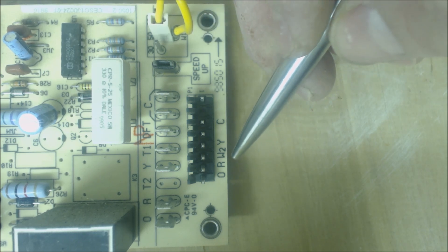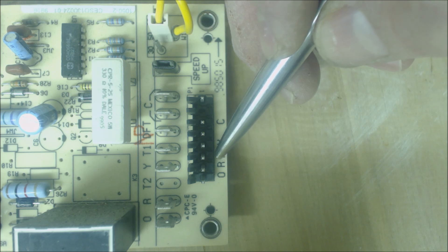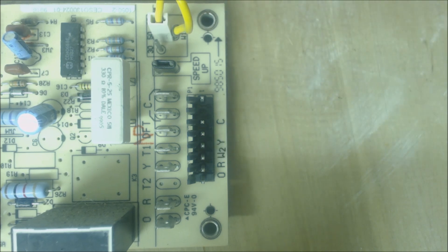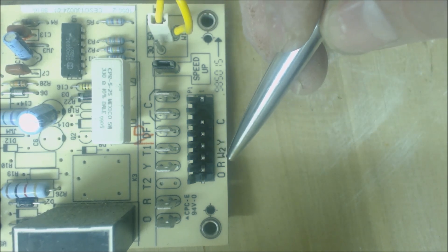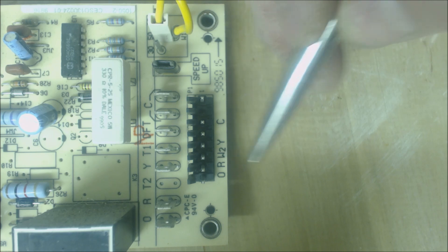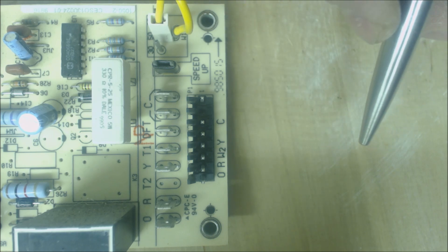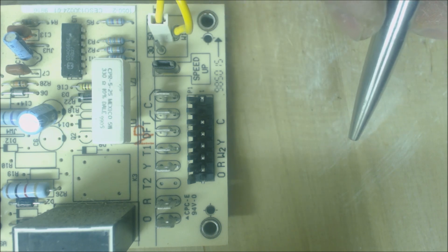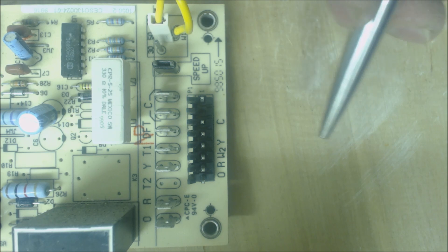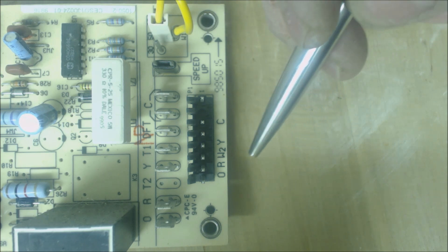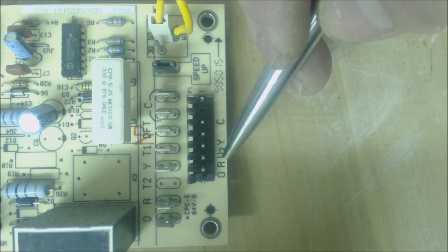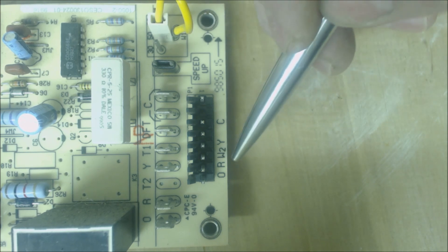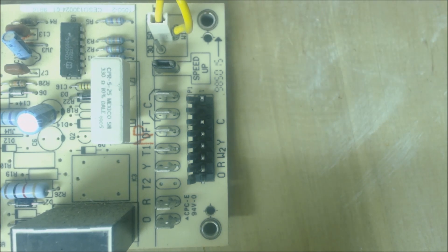W2 is a 24 volt signal wire coming back out, sending 24 volts to the indoor air handler to tell it to turn electric resistance on or an auxiliary heat source. That happens during the defrost cycle only. That's the only time this is an output wire.